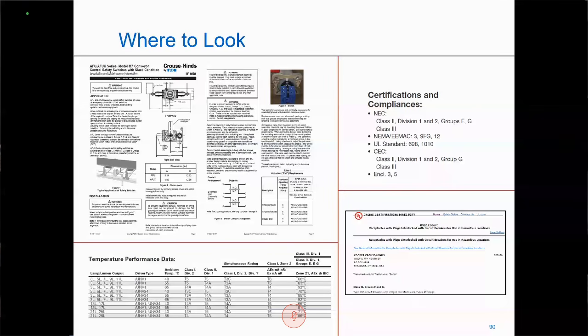When you have the larger junction boxes or motor starters or panel boards, typically with those, you'll see manufacturers have torque ratings for those. So they'll have to be tightened to the proper torque ratings. Usually those torque ratings can vary per manufacturer and type of box, but they're usually going to fall somewhere around that 50 to 55 pound of torque force.